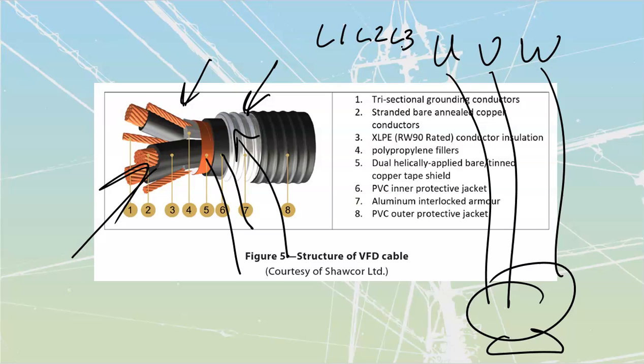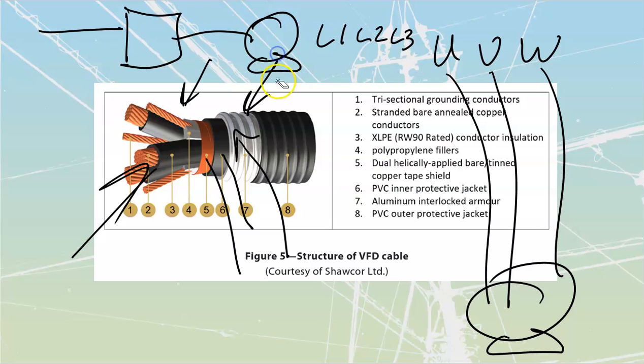I can run a 240 volt motor off of it, provided that I tell the drive that I'm not going to be running 600 volts. I'm just running 240 volts off of it. So it makes it really handy on some installations where you might have a 600 volt system, and then there is a piece of equipment that comes in as a 208 volt motor. It turns out you don't need an isolation transformer or anything like that. You're just going to take that VFD at 600 volts.